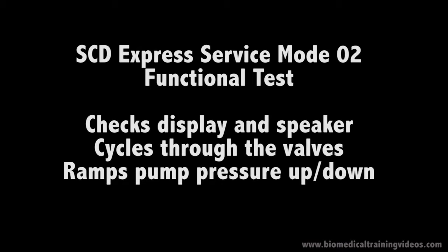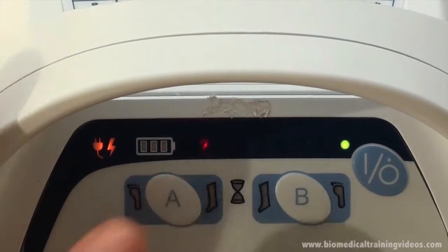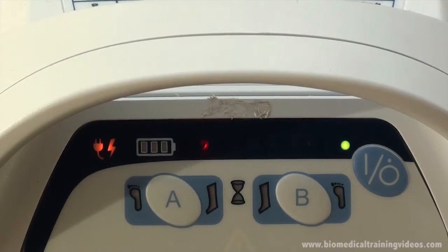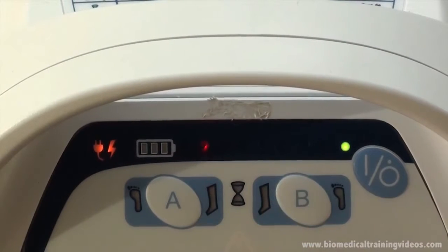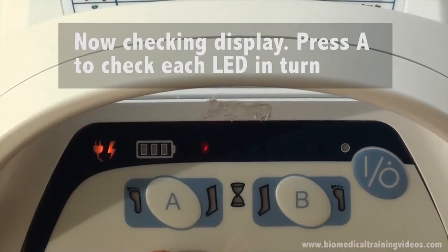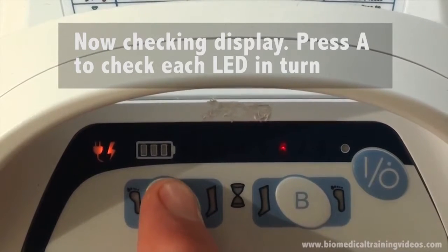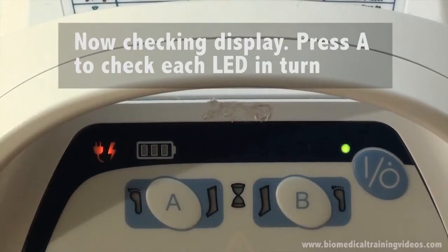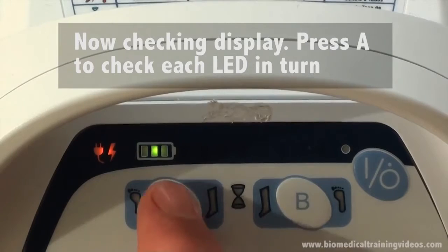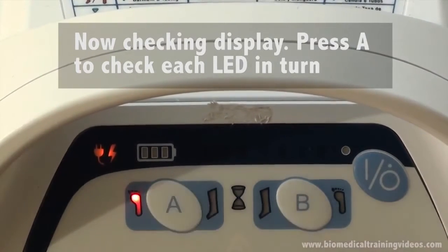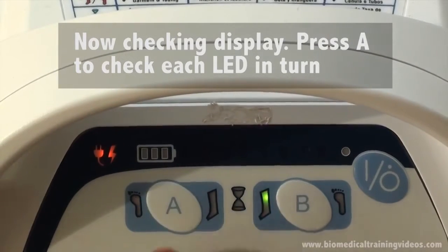So we'll cover service mode 02, the functional test. This is a check of the display, speaker, and the valves and the pump. So test 2, and we press B to start the test. You'll hear the valve cycling. I've sped this up a little bit so it sounds a bit odd, but each press of the A button will check each of the LEDs in turn. Red and green segments of each. So you can check every single LED to make sure they're okay. And you're obviously hearing the beep of the speaker at the same time.